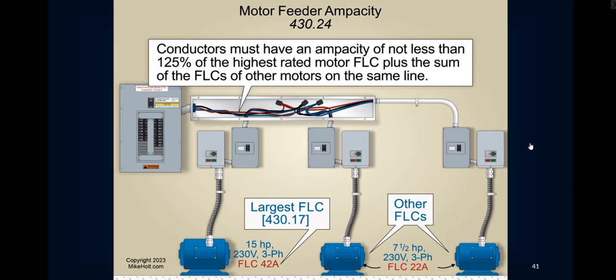How do you decide what size wire to run to all of these? And then you're able to split off. And what size overcurrent protection device do you put in that panel? This is how you do it. Essentially what you're going to do is go to the tables in the NEC, take the motors, and go, okay, this motor, if you look at it, it says largest FLC. So the motor that is a 15 horsepower motor, 230 volts, three-phase, the FLC is actually 42 amps. Keep in mind, whenever you see a bunch of motors like that, especially in a test question, just because it's the highest horsepower doesn't mean it's the highest ampacity. But 15 horsepower for a 230 volt three-phase, that's the largest one. The other one there is 7.5 horsepower, and it's 22 amps. So we're going to take that largest amount.